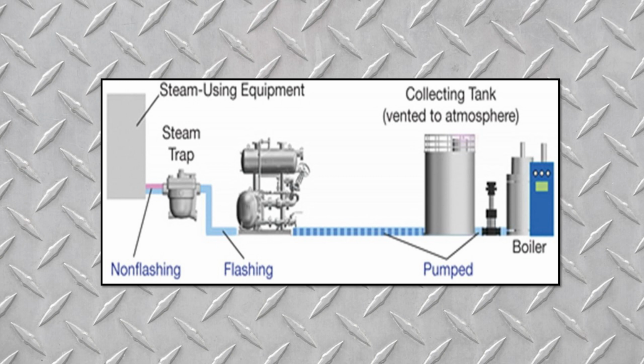So now, as we return condensate to the tank, if it cools a little bit, that's okay because we're getting farther away from the boiling point. It's normally still under pressure and can flow back to a condensate tank, even if that tank is a little bit above atmospheric pressure. If needed, we see an occasional pump or two around a plant to help push the condensate back. Now remember that we do not want to return condensate if it is contaminated in any way, or if the distance you have to push it is prohibitively long and it would not pay to return it. Sometimes you'll see a condensate return system not in use because it was tried and failed and they decided not to continue with it.